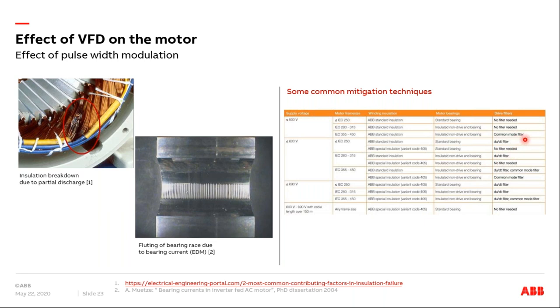So some of this, just as an example here for the insulation side, we could use common mode filtering. So that's one. I think you don't need to use it for all applications, but for some applications. And here you can see that in some motors, or certain sizes of motor, we use special insulation, not the standard insulation, to make the issue of insulation stress less of an issue.